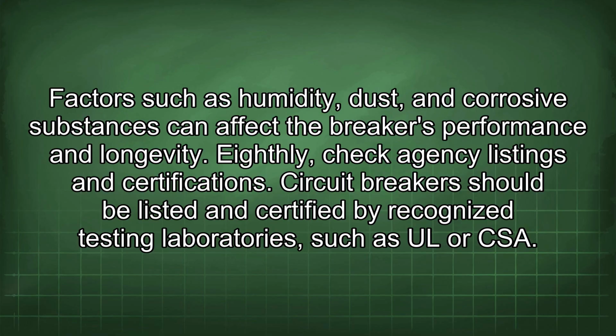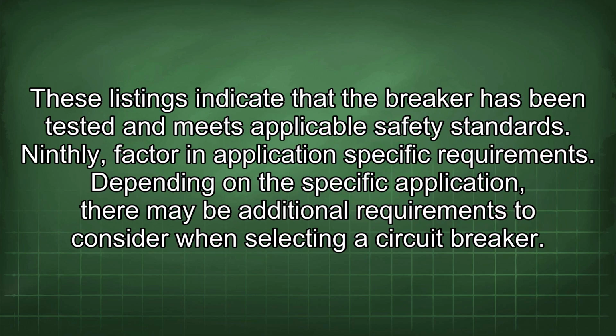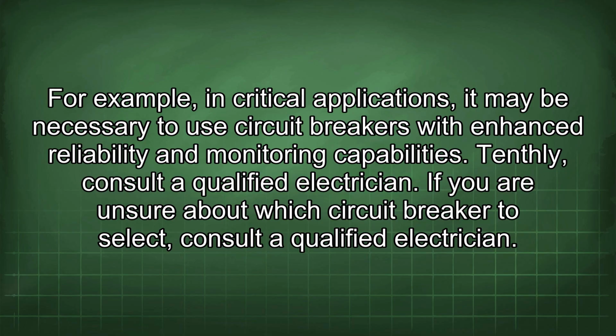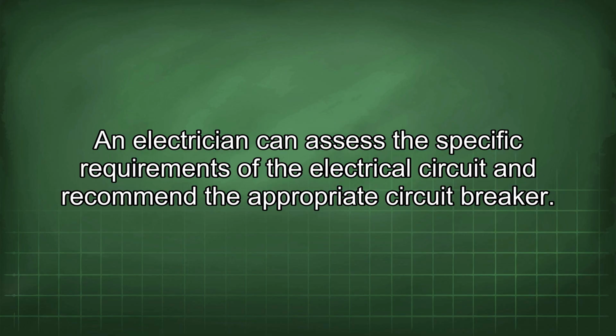Eighthly, check agency listings and certifications. Circuit breakers should be listed and certified by recognized testing laboratories such as UL or CSA. These listings indicate that the breaker has been tested and meets applicable safety standards. Ninthly, factor in application-specific requirements. Depending on the specific application, there may be additional requirements to consider when selecting a circuit breaker. For example, in critical applications, it may be necessary to use circuit breakers with enhanced reliability and monitoring capabilities. Tenthly, consult a qualified electrician. If you are unsure about which circuit breaker to select, consult a qualified electrician. An electrician can assess the specific requirements of the electrical circuit and recommend the appropriate circuit breaker.